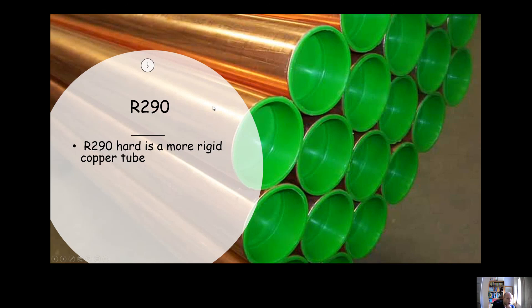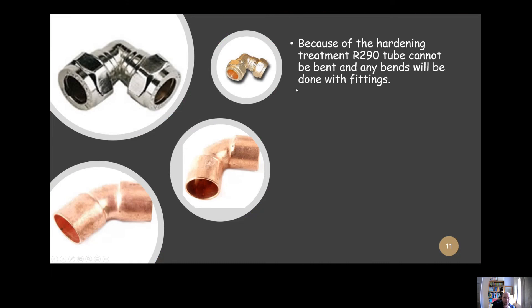R290 is known as hard copper pipe. This is actually going to be treated to make it hard. The walls are generally going to be a little bit thinner, but the external bore is going to be the same as R250. The common pipe sizes are again going to be 15mm, 22mm, 28mm. You can't bend R290, not using the machine. Any changes of direction would have to be done with fittings.